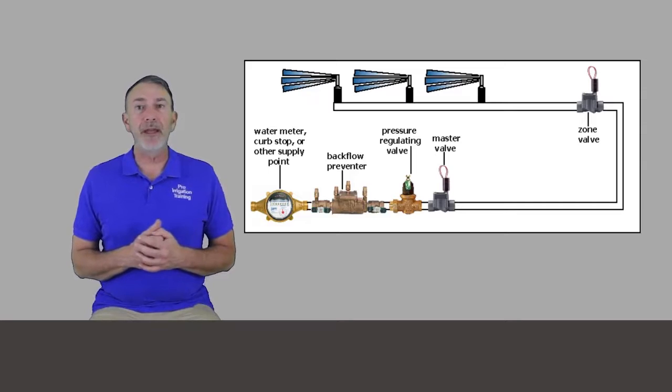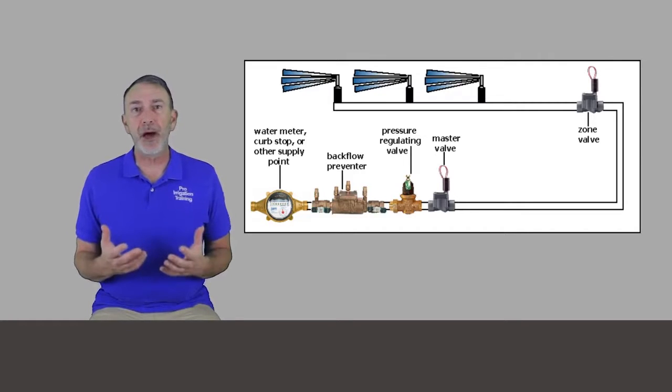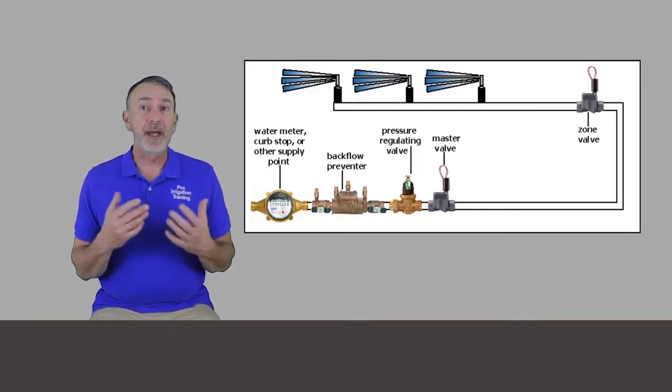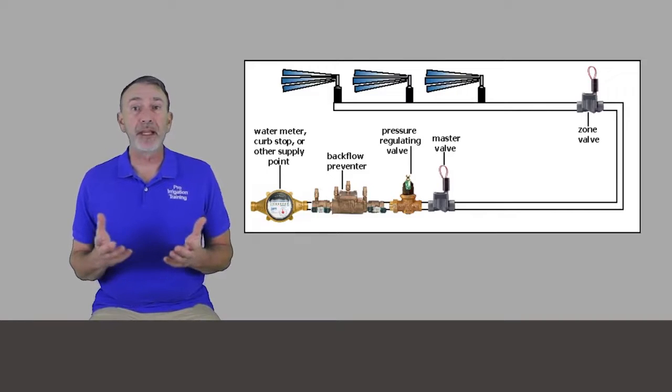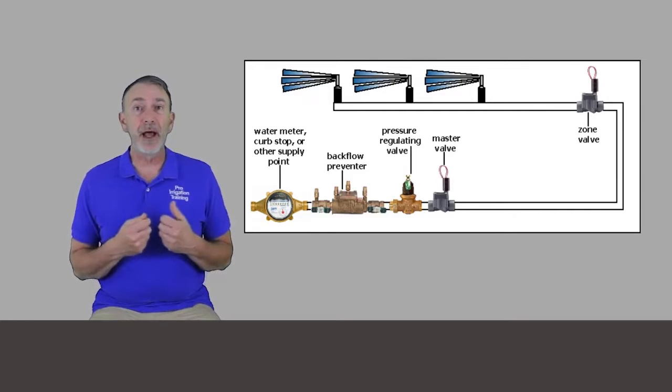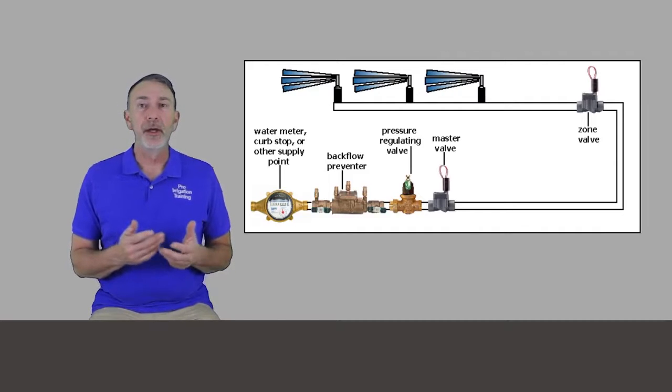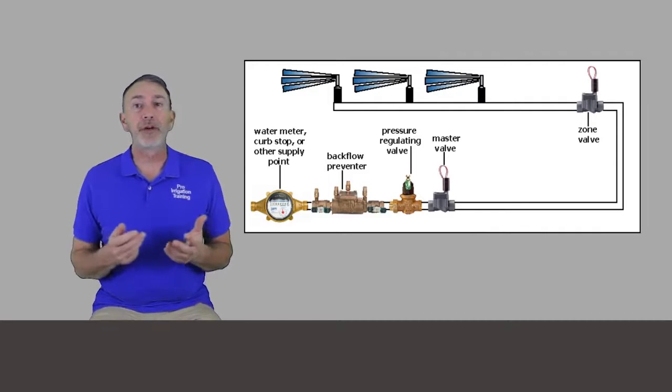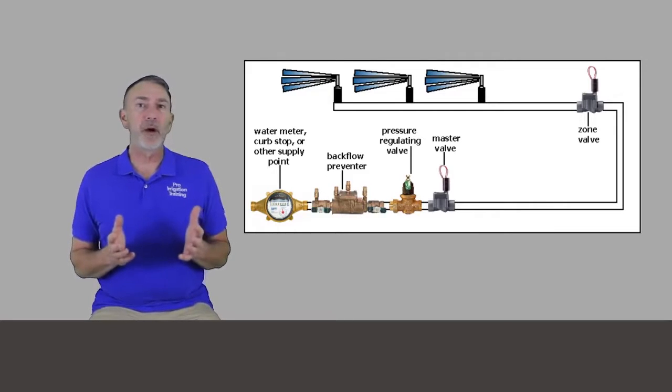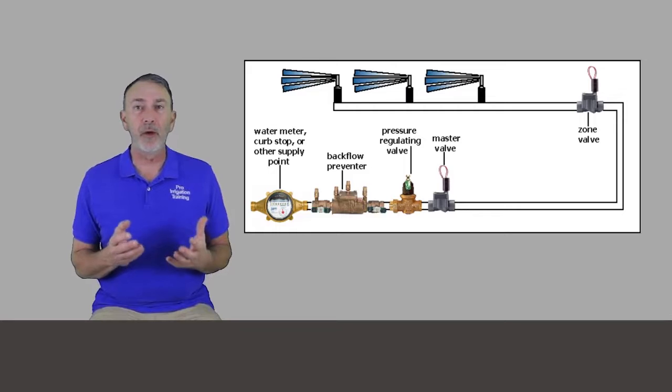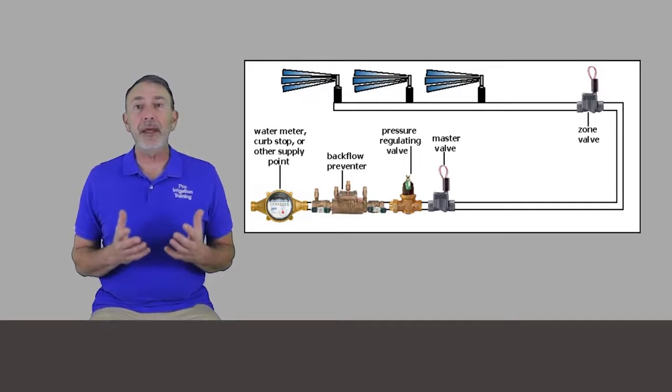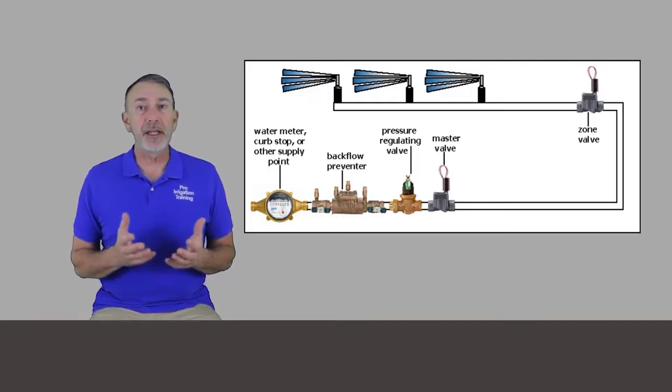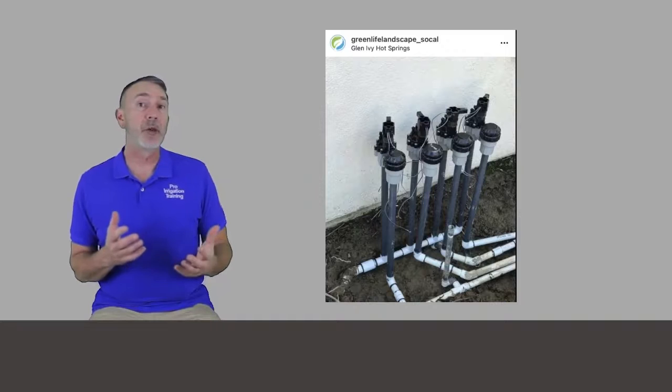National codes say that once water has entered into irrigation piping, then it's unfit for human consumption. And what this type of backflow prevention unit does is to prevent water from being sucked back into the drinking water supply. It also prevents it from being pushed back into the drinking water supply, should the lines be back pressured in some way.